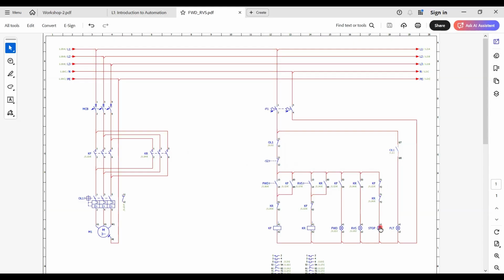So which means when you stop the whole circuit by pressing this one and release, normally the circuit, the red light is lit. So that is an indication the circuit is at stop position. So when the circuit is stopped, either you can press for forward or reverse. When it is running in the forward direction, you cannot press the reverse push button because this is interlock.